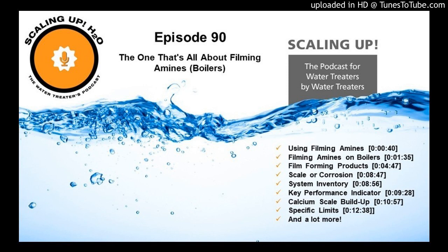And a caveat to that is if the optics with your customer are such that, let's say they come to you and they're like, well, we know we have a scaled system and we have a boiler inspection in 2 months and we want it to look better. Do you have something to clean it out? Well, the filming amines will work, but will they work in 2 months so that optically you look like a hero? Maybe, maybe not.